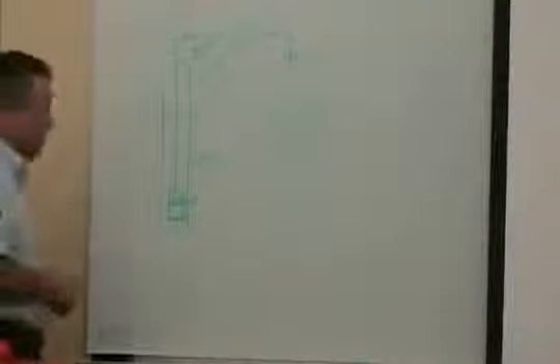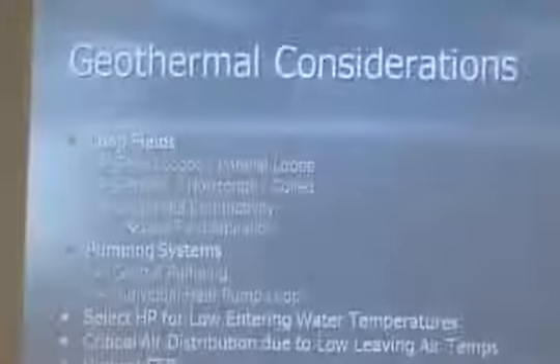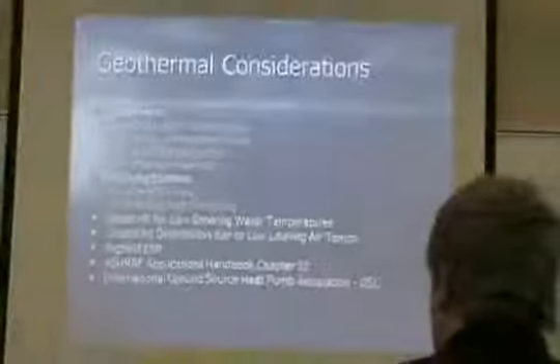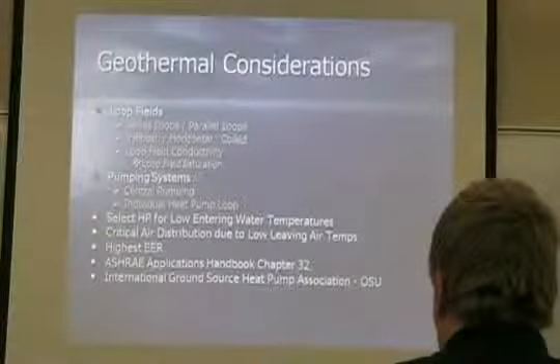Steve, do you see a lot of that in commercial applications? Not in commercial applications, just because of the demand and how you get the water back in the ground. Those are three types of geothermal loops: horizontal, vertical wells, slinky pipes, and pond water. And there are people out there making heat exchangers to drop in ponds as well. There are drawbacks, like algae, things like that. Well, the algae not so much, but the mussels.